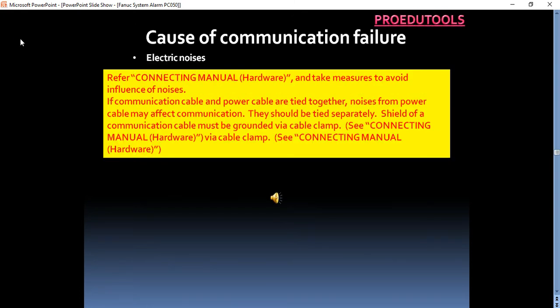Electric noises. Refer connecting manual hardware and take measures to avoid influence of noises. If communication cable and power cable are tied together, noises from power cable may affect communication. They should be tied separately. Shield of a communication cable must be grounded via cable clamp. See connecting manual hardware.